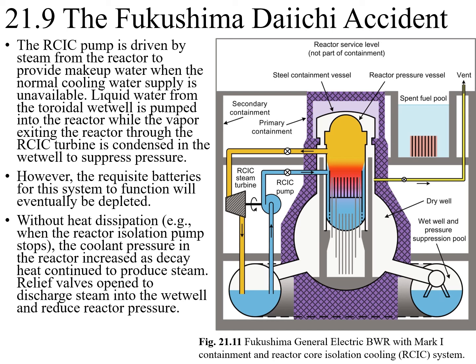If there is any leak inside the primary containment, the steam will be collected and pushed into this wet well. This wet well has the shape of a donut surrounding the primary containment. It is filled with cold water. So when the hot steam comes in contact with the cold water, it will be condensed in order to reduce its pressure.